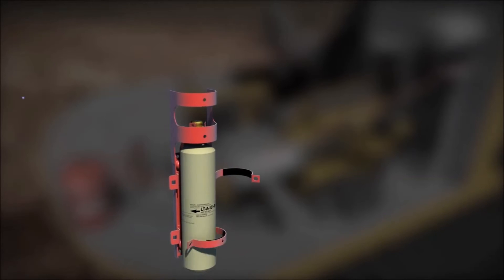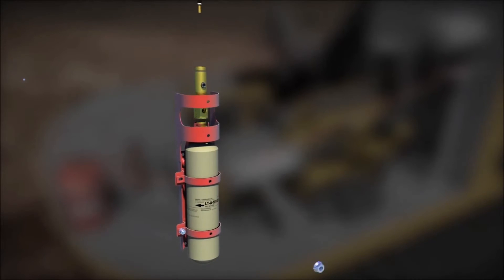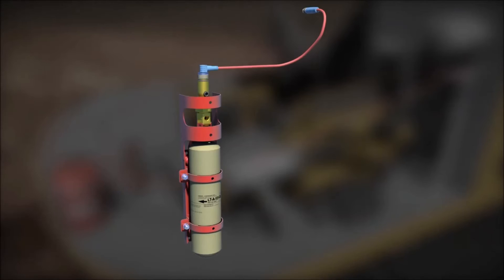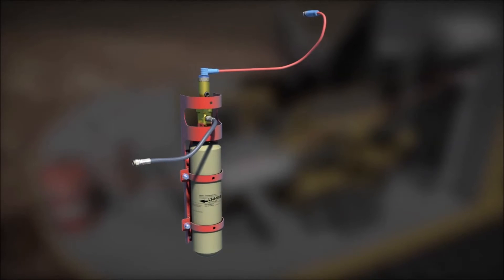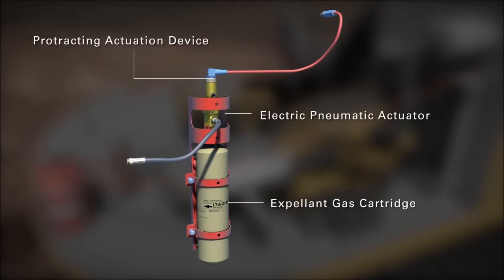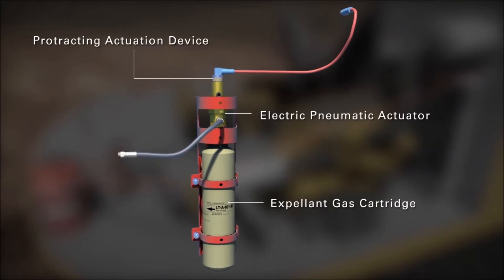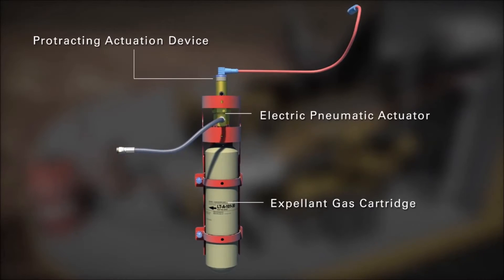The protracting actuation device or PAD is installed in the electric pneumatic actuator which is mounted on the expellent gas cartridge located near the agent tank. The release circuit provides supervision from the CheckFire 110 system to the electric pneumatic actuator. The system can actuate a maximum of two electric pneumatic actuators.